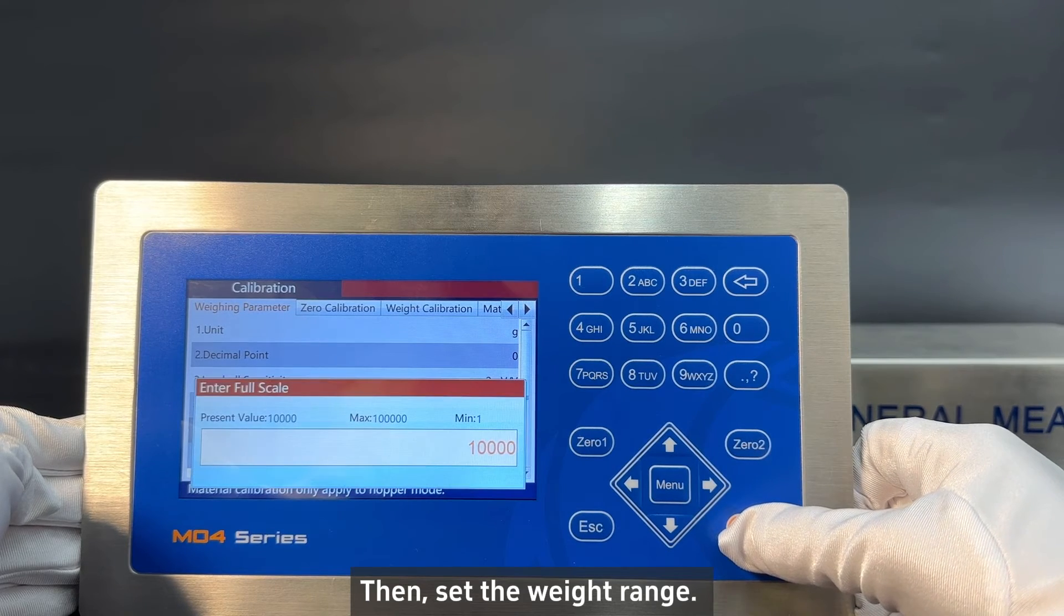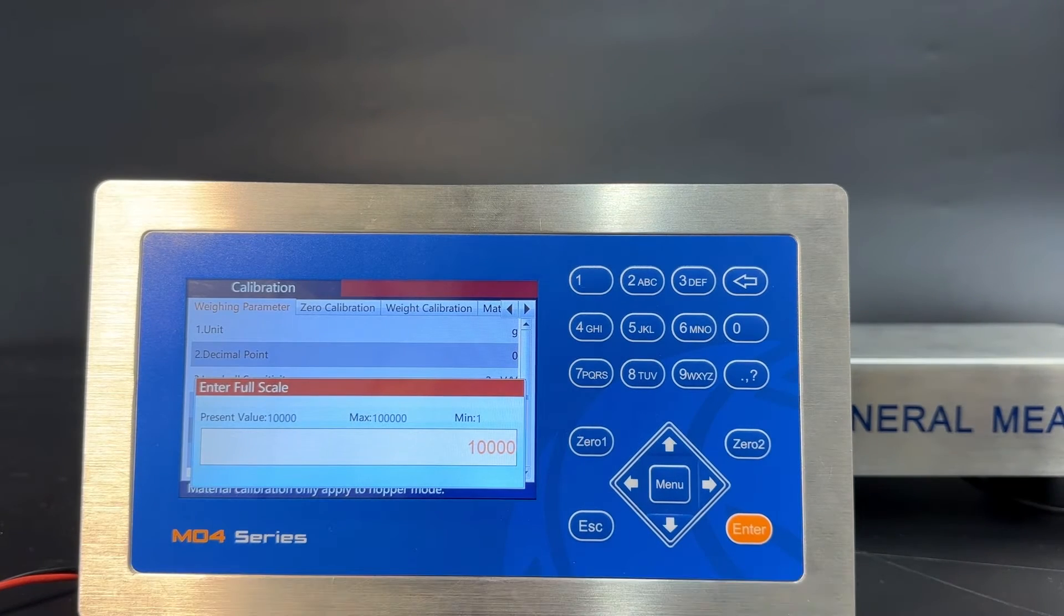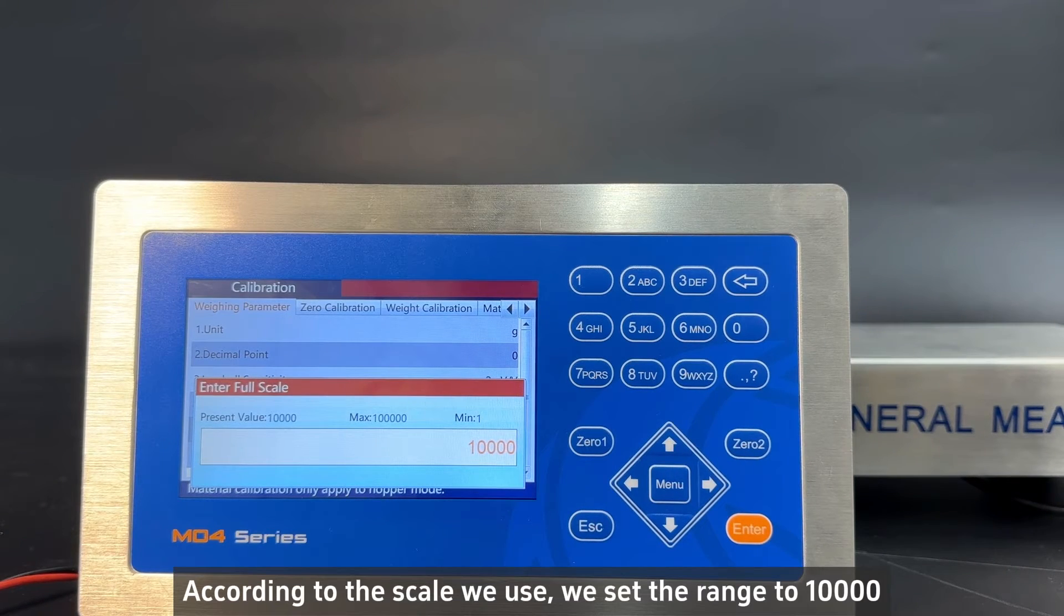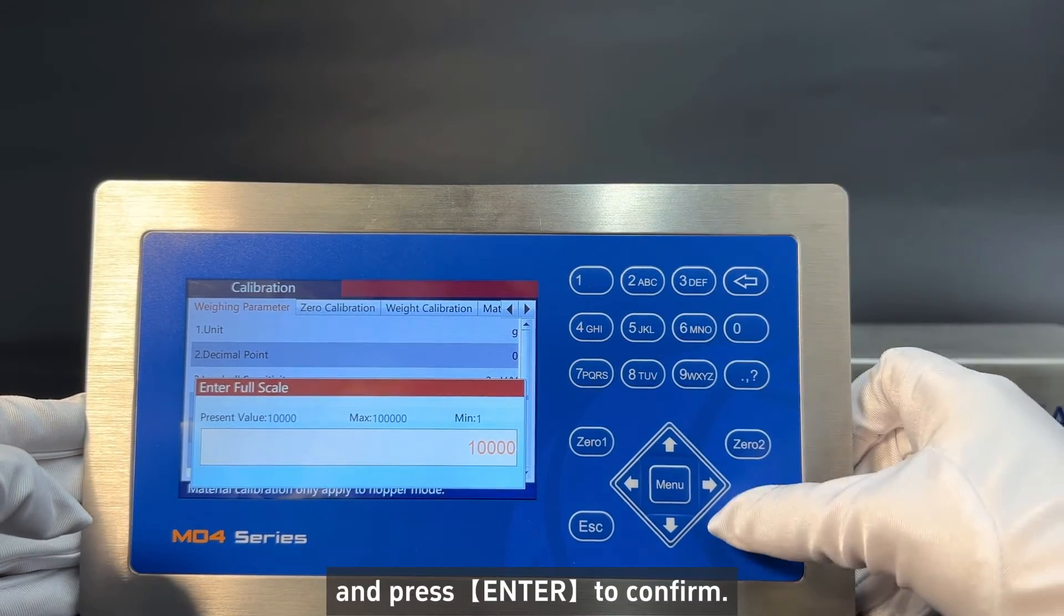Then set the weight range. Generally, we set it as the maximum weight of the load cell. According to the scale we use, we set the range to 10,000. And press enter to confirm.